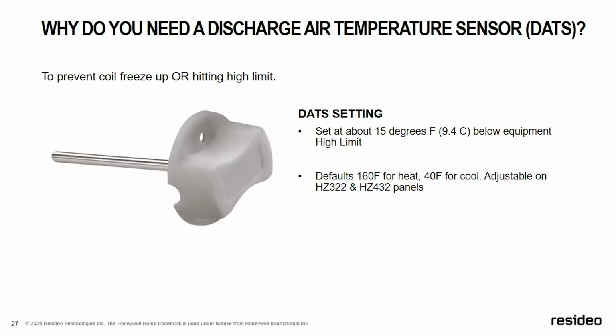The reason for that is if your smallest zone is calling and your discharge air temperature sensor goes off, it's going to click out the burners. On a clean furnace with a clean coil and a clean filter, you're going to get 8 degrees of rise. As your filter gets dirty, that rise is going to go up. Typically, when you've got a dirty filter, you're going to get 12 degrees of rise. Now, if you have a plugged filter, you're actually going to want this to go off, because that's when you want to get out there and do the maintenance.